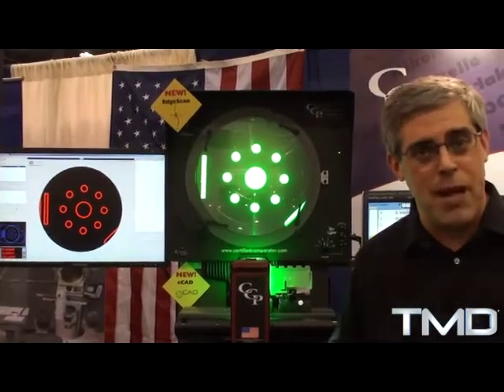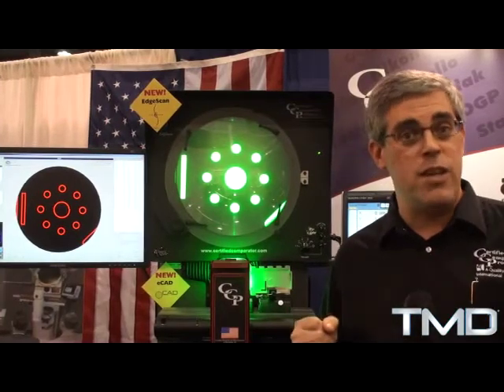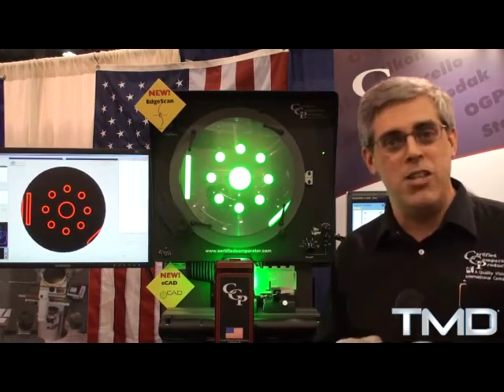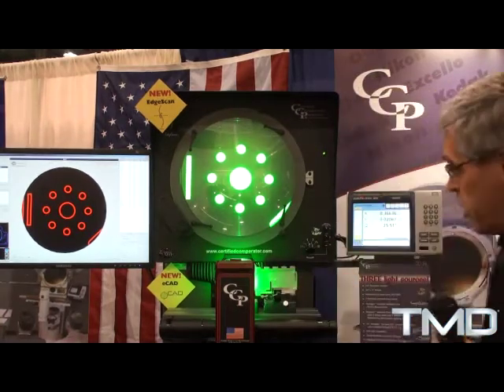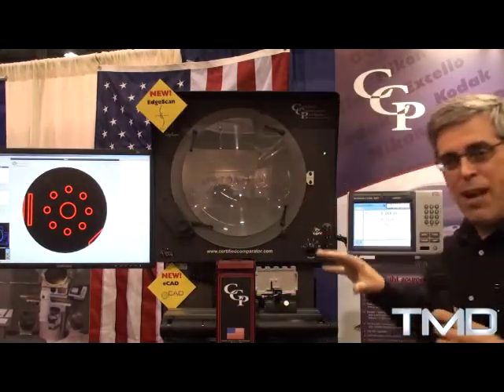We made the lighting much better — we went to all LED lighting. The main thing with optical comparators is there's never quite enough light, and there's tons of light now with the LED lights. LED lights are rated to last 11 years, 24/7, with lots of light and very little heat emitted on the part versus the old tungsten halogen or mercury lights.